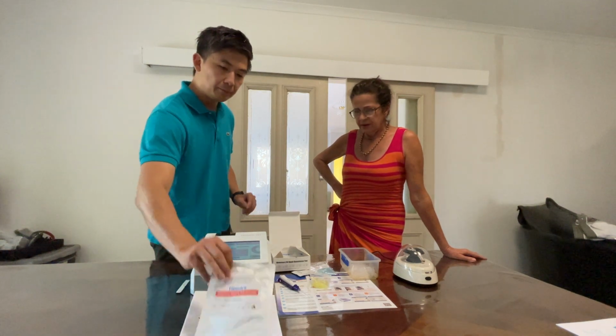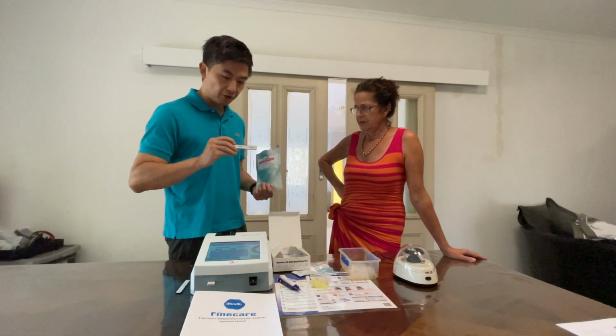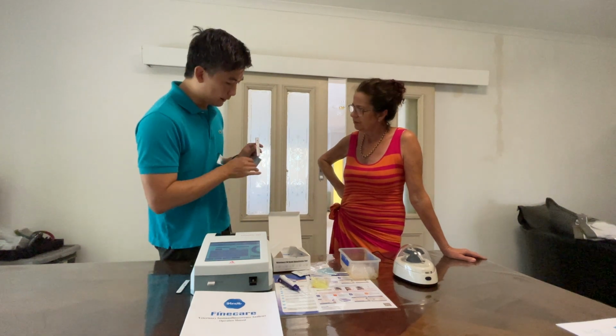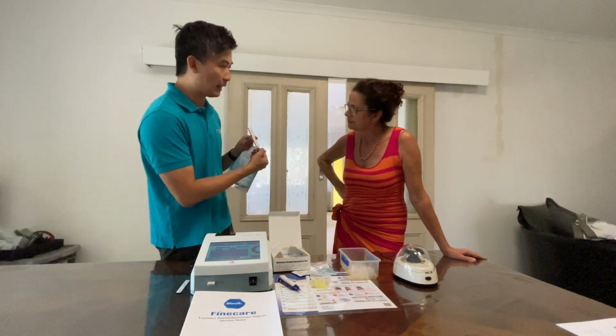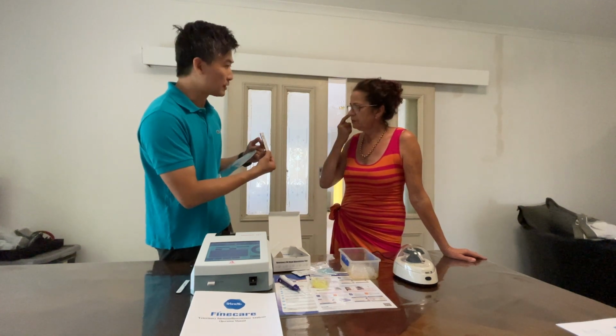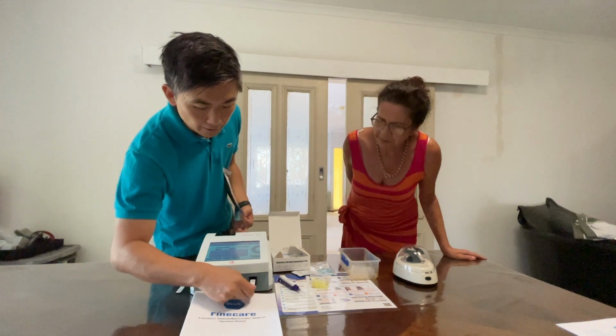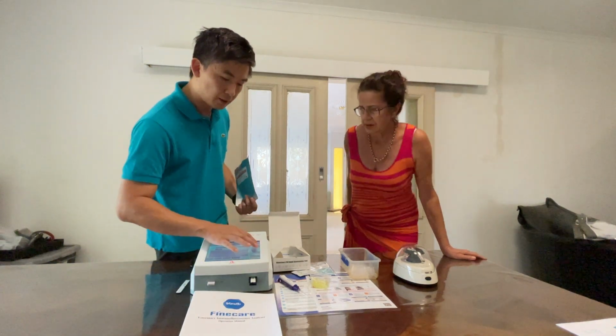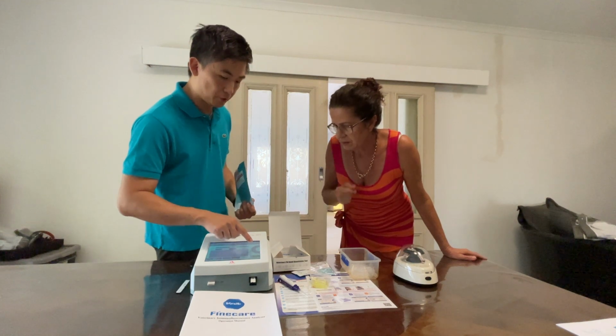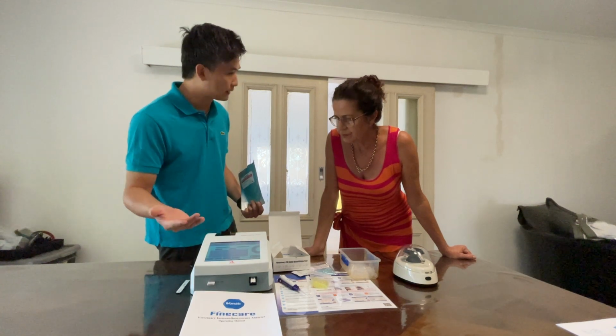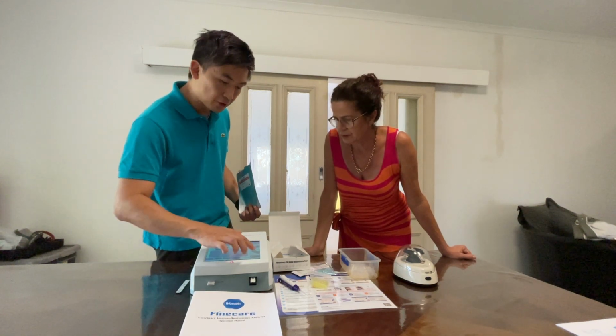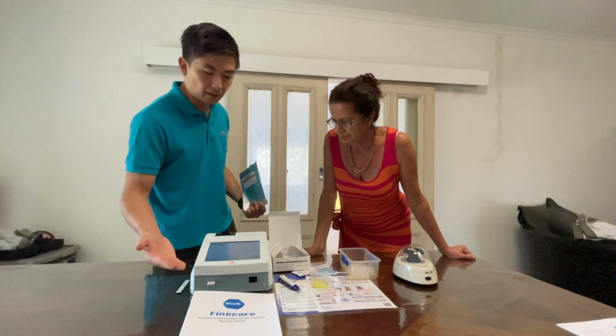Now what we have here is the control reading card. This is a calibration card to make sure the test we're running is accurate. You just take it out from the foil pack. You can see that one side is textured, and that's just for you to hold on to. The other end goes into the machine, facing up, into this slot here, all the way in. Then here you have two options. One is a quick test, one is a standard test. Since we're only doing a calibration, I think a quick test is good enough. Yes. Then you just press start test. It should only take about 5 seconds.